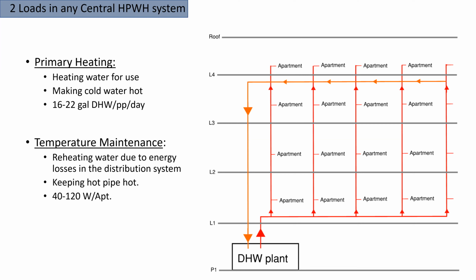On the temperature maintenance side, this is really just keeping the line primed. The losses here are an area that needs more research to understand the range of values, but we've found in the field between 40 and 120 watts per apartment is the metric we've been using. This is important because we've got to continue driving down these temperature maintenance losses, since they make up a significant fraction of the total load.